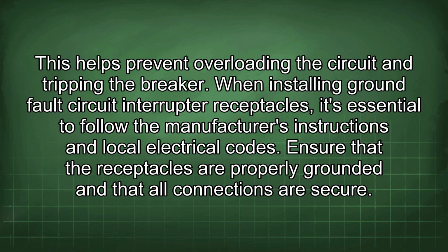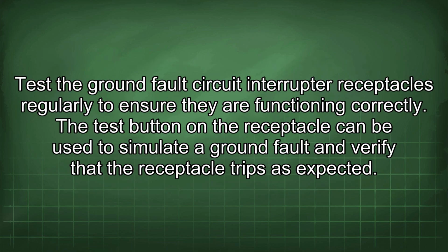When installing ground fault circuit interrupter receptacles, it's essential to follow the manufacturer's instructions and local electrical codes. Ensure that the receptacles are properly grounded and that all connections are secure. Test the ground fault circuit interrupter receptacles regularly to ensure they are functioning correctly.